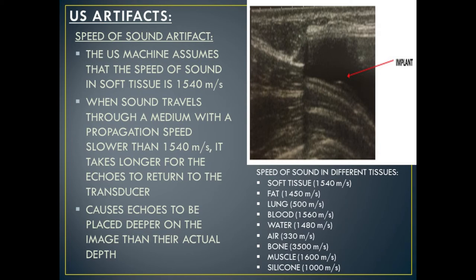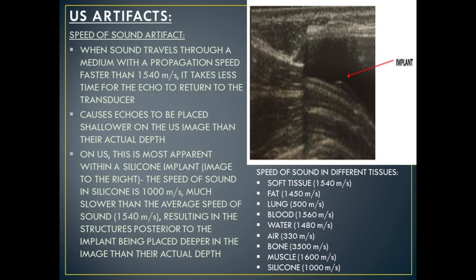When sound travels through a medium with a propagation speed slower than 1540 meters per second, it takes longer for the echoes to return to the transducer than the ultrasound machine is expecting, causing echoes to be placed deeper on the image than their actual depth. When sound waves travel through tissue with a propagation speed faster than 1540 meters per second, it takes less time for the echo to return, causing echoes to be placed shallower than their actual depth. This is most apparent within a silicone implant — the speed of sound in silicone is 1000 meters per second, much slower than the average 1540 meters per second, resulting in structures posterior to the implant being placed deeper in the image than their actual depth.